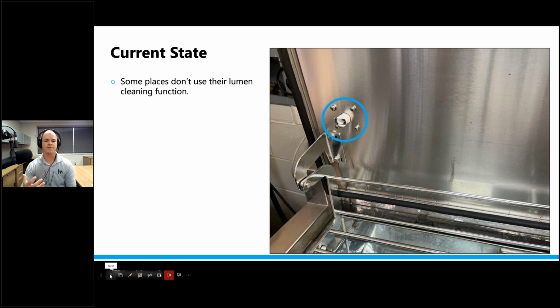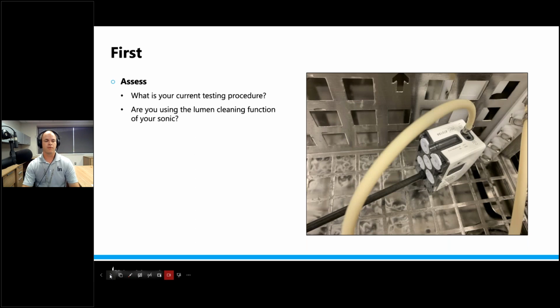So if you have an ultrasonic cleaner and you haven't been using that lumen cleaning function, maybe just go and see what your equipment is and if it even has that functionality, because if it does, you might be missing out on some automated cleaning function there that would really help you produce cleaner instrumentation at the end of your process. So first, that's what we're going to start with. We're going to assess what our current testing procedure is and whether or not we're actually using that lumen cleaning function. As you can see there with the picture, it's a robotic arm or robotic endo-wrist instrument that is hooked up to the lumen cleaning accessories within the ultrasonic cleaner.